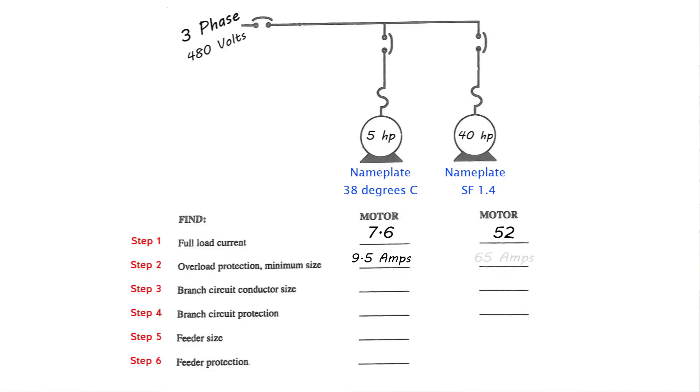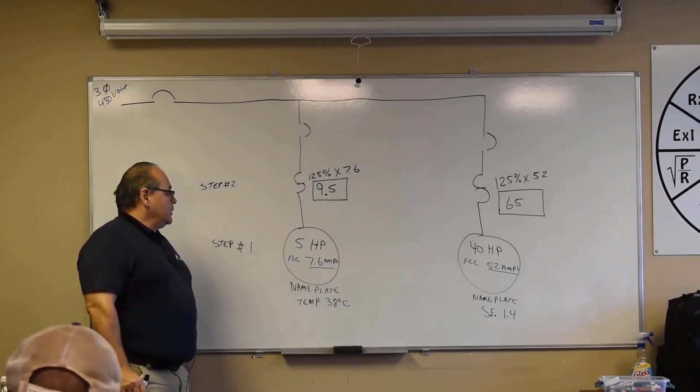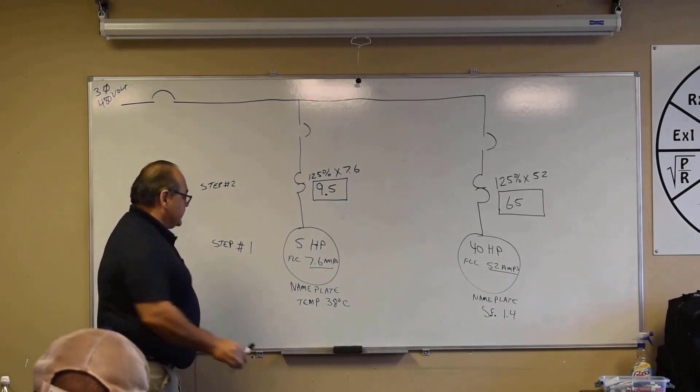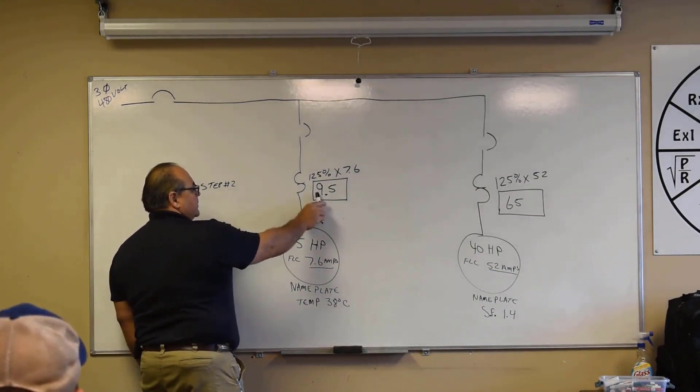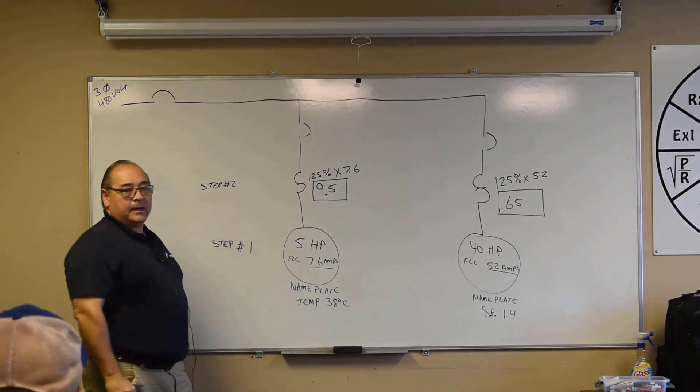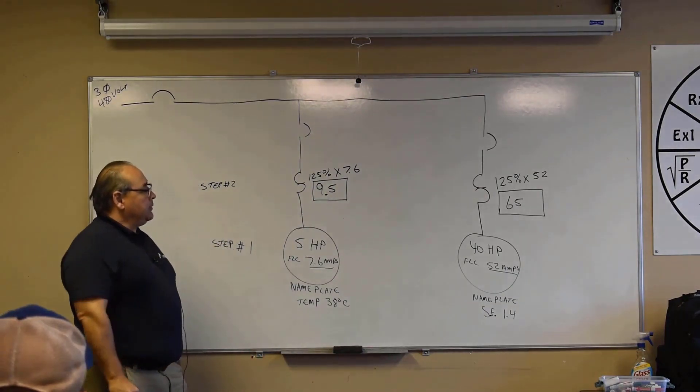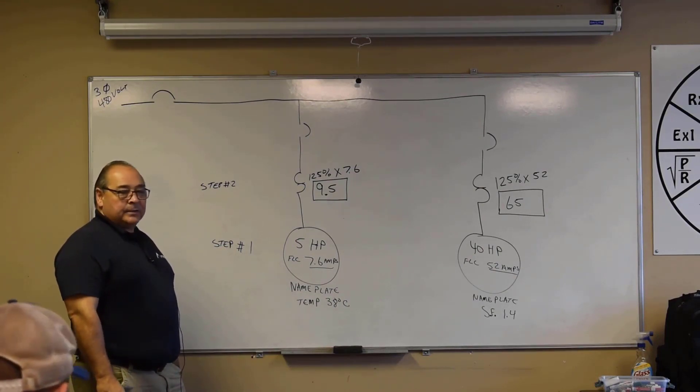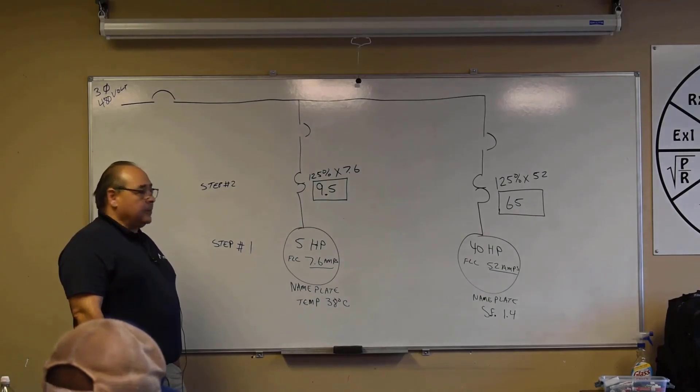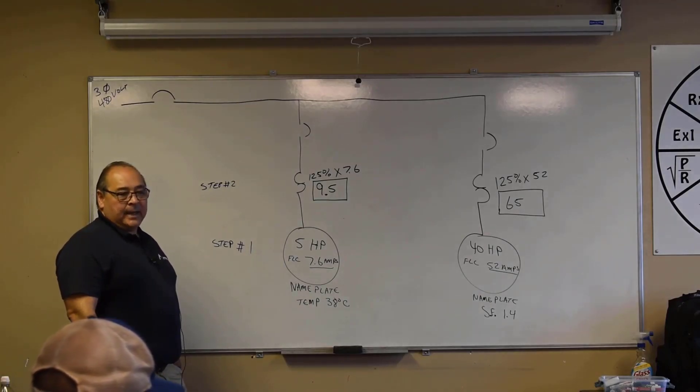Okay, that's step number two. So what we can look at, just kind of get our point of reference, we got a 7.6 amp motor, a full load current, it's going to trip once it gets to 9.5. We got a 52 amp motor over there, it's going to trip once it gets to 65 amps. I tell people all the time about motors, motors are dumb. There is no intelligence to a motor. A motor will run until it burns itself out. We have to provide the intelligence for it, right? We have to provide the protection for it. A motor will just run and run and run.